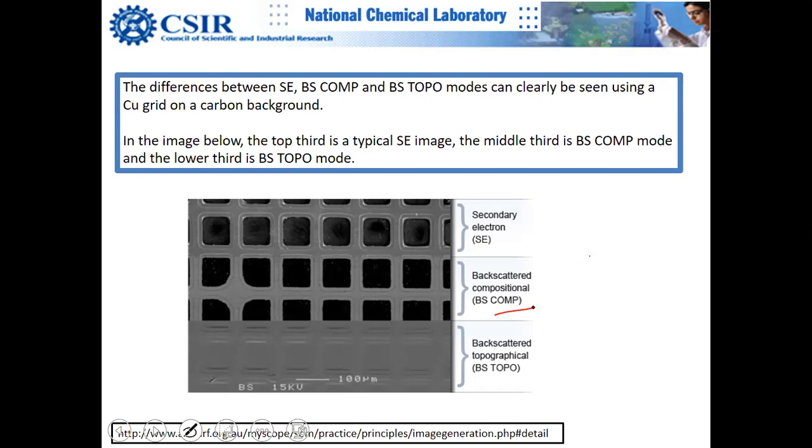And we have already discussed that secondary electrons have better topography information because the resolution is better. And another thing is that subsurface information is more prominent in backscattered electrons. So you can see that it is there, but it is not as good as you would see in secondary electrons, right? So it is normally not recommended that you use it, for obvious reasons.